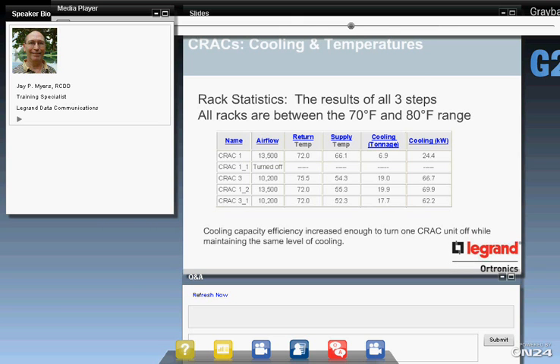So the return air is getting warmer, which is what we want. We want the hottest possible air going back into the CRAC units. If you have, say, a 20-ton CRAC unit, and the temperature difference between the supply air and the return air is only 10 degrees, you may only be getting 10 tons of cooling out of that CRAC unit. But if you can raise that temperature up to 80 or 90 degrees, by keeping the air from being diluted by the cold air, you may get 25 or 30 tons of cooling out of your 20-ton unit. So that's also a hidden efficiency that's not so obvious.